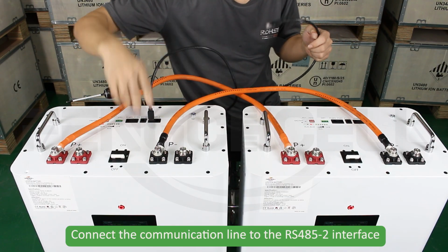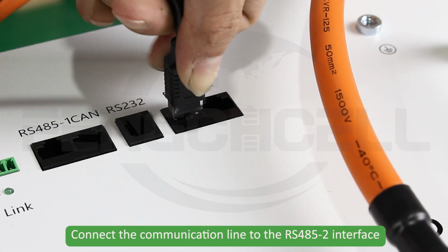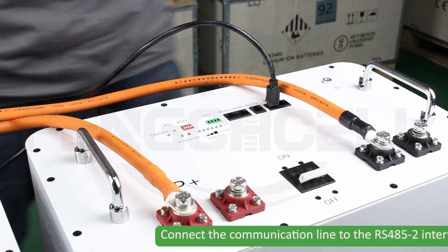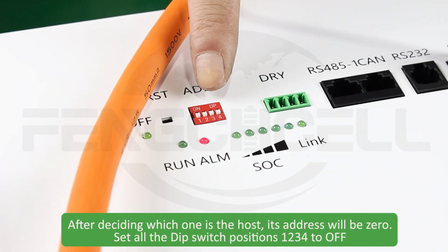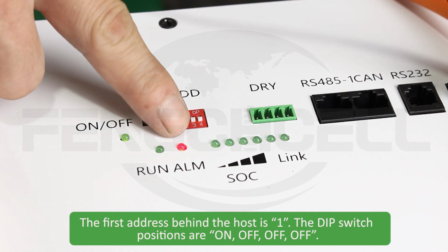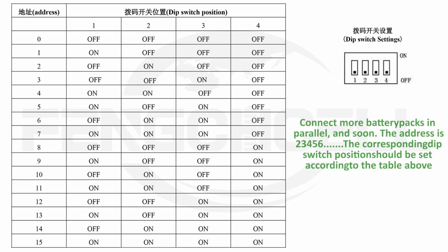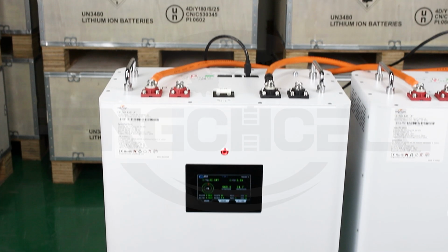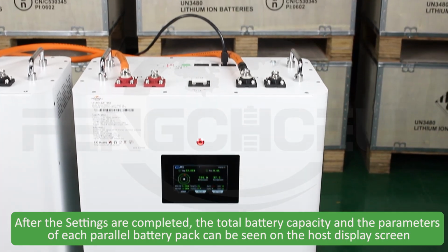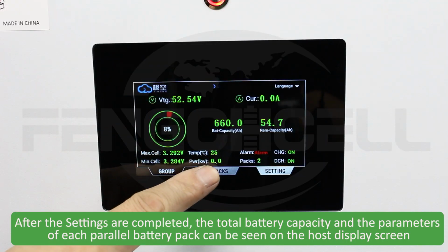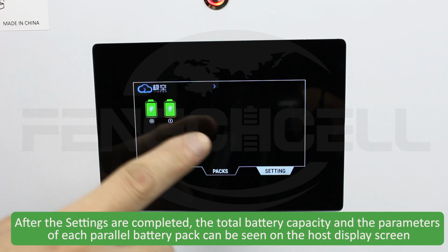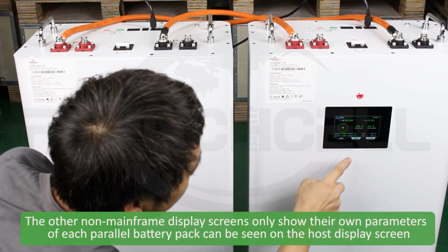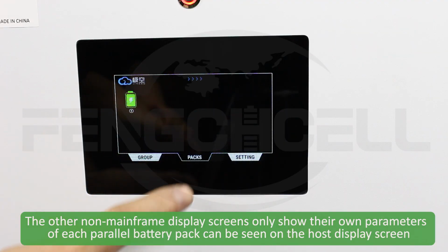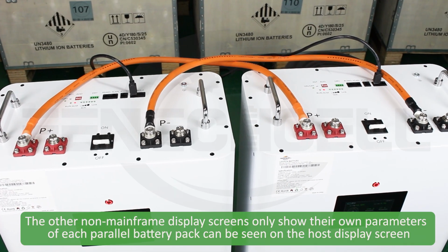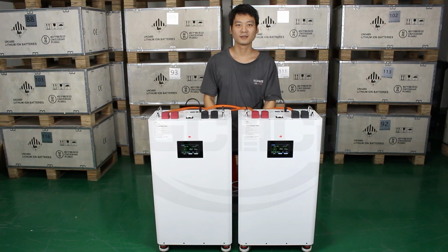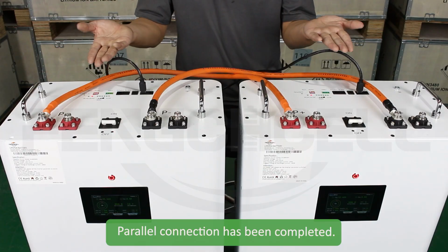Connect the communication line to the RS485 interface. The first address behind the host is 1. The dip switch positions are on, off, off, off. After the settings are completed, the total battery capacity and the parameters of each parallel battery pack can be seen on the host display screen. The other non-mainframe display screens only show their own parameters. Parallel connection has been completed.